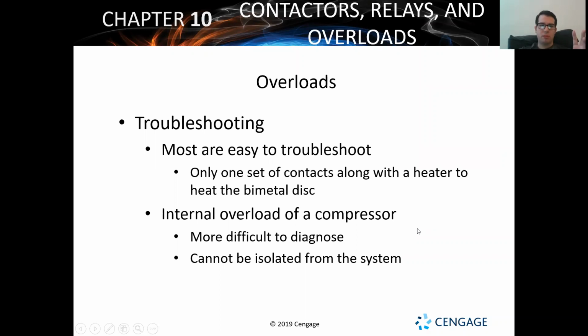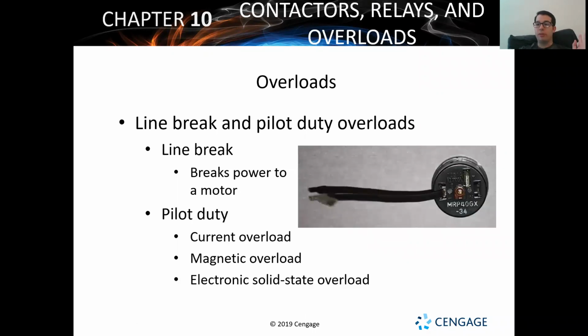This doesn't go into it as I'm used to, as the other slides went a little more into the different styles of the pilot duty. Basically, with current, we're sensing amperage. It's going to be rated for a certain amount of amperage. When it senses that amperage, as far as a startup or anything like that, it will disconnect the system. It'll shut the motor down if it's drawing too much. A magnetic overload is going to be where a coil is causing magnetism too greatly.